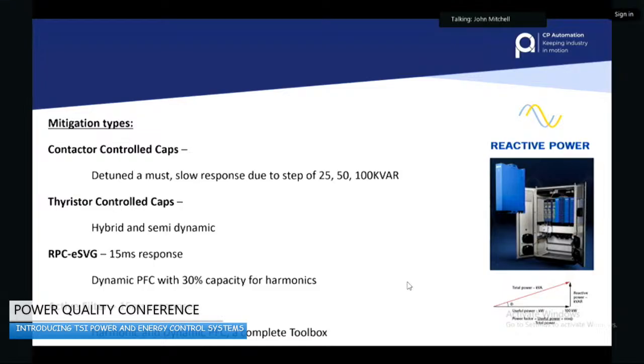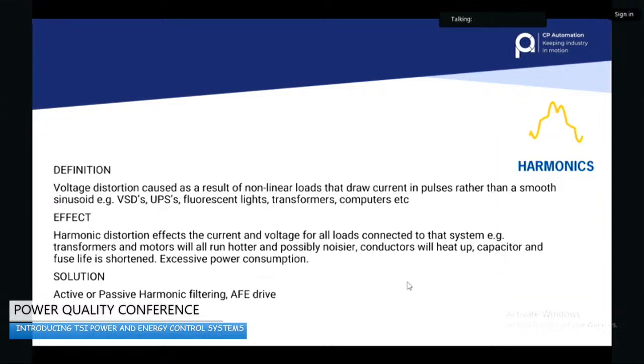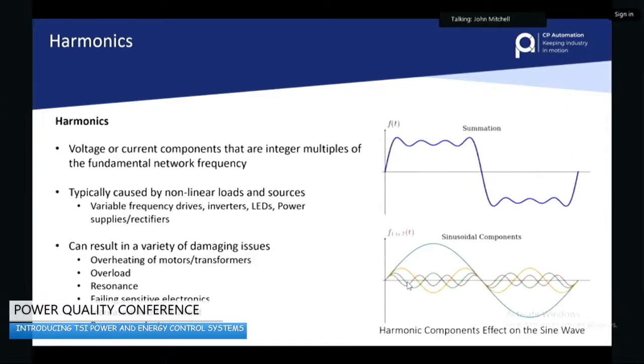And then the other way is to do it with an active harmonic filter, and that's a whole topic as well, but we'll get into that. Harmonics are caused by drawing nonlinear loads. So back in the day, we didn't have harmonic problems because we just had direct online motors or star deltas. We moved to soft starts and then we moved to VSDs, and these are causing harmonic issues. There are technologies that are less harmonic creating, but there are ways to mitigate that. If you get too many harmonics on your system, eventually it would become a square wave, and that's not good for any piece of equipment running on AC.